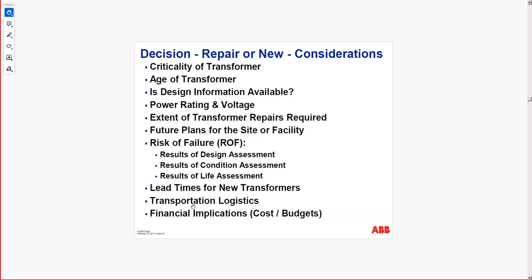Yes, you may want a transformer, you may have the budget, but you should consult with the potential providers about the delivery time, because this is a long lead item. A new transformer will not just come on site the next day after putting in a PO. It takes time to manufacture, to test, to actually have it delivered. Transportation should be done with an impact recorder. The impact recorder will record any impact, and if it's anything larger than acceptable, the transformer needs to be tested again, shipped back, or repaired on site. Okay, so these are the factors for the decision between repair or new.